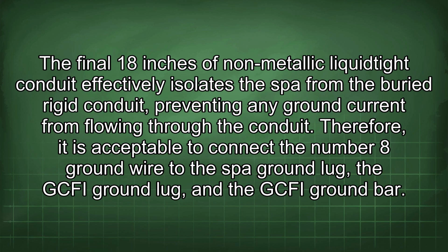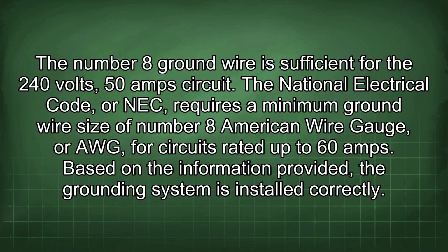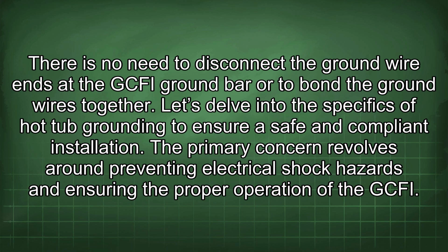Therefore, it is acceptable to connect the number 8 ground wire to the spa ground lug, the GFCI ground lug, and the GFCI ground bar. The number 8 ground wire is sufficient for the 240 volt, 50 amp circuit. The National Electrical Code, or NEC, requires a minimum ground wire size of number 8 American wire gauge, or AWG, for circuits rated up to 60 amps. Based on the information provided, the grounding system is installed correctly. There is no need to disconnect the ground wire ends at the GFCI ground bar or to bond the ground wires together. Let's delve into the specifics of hot tub grounding to ensure a safe and compliant installation.